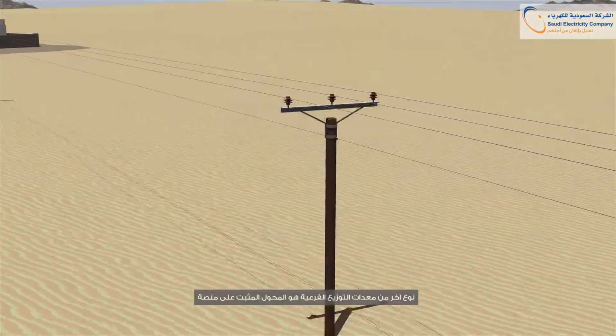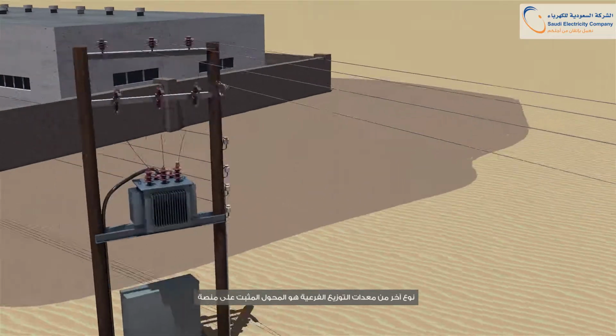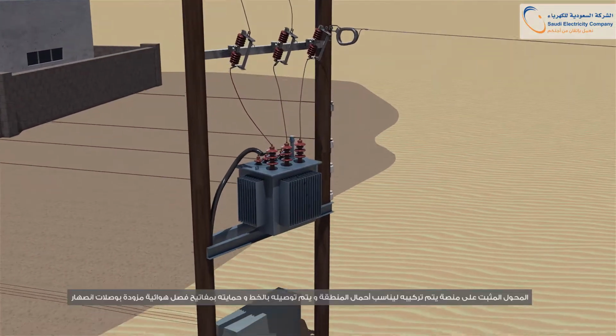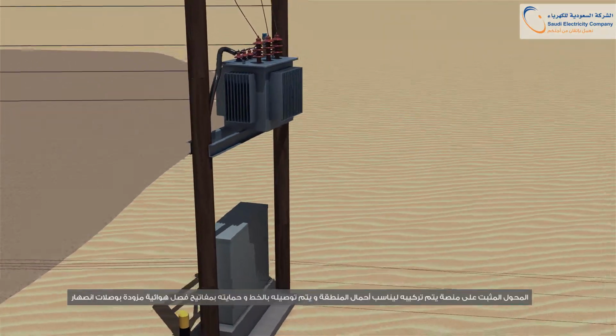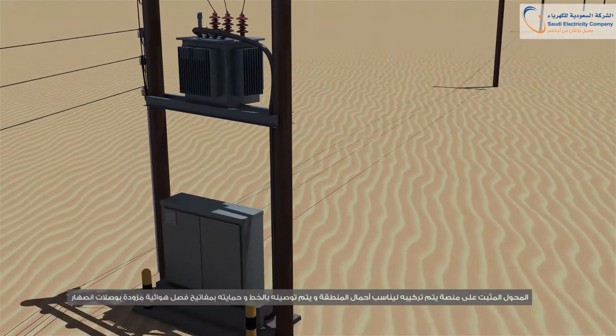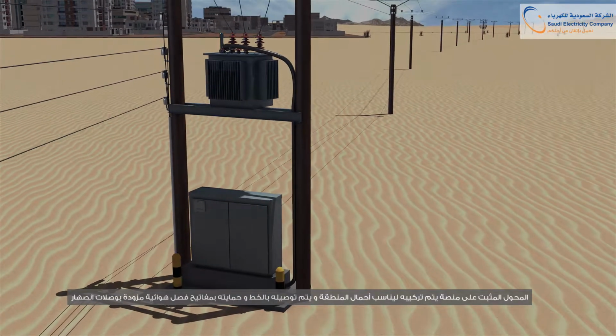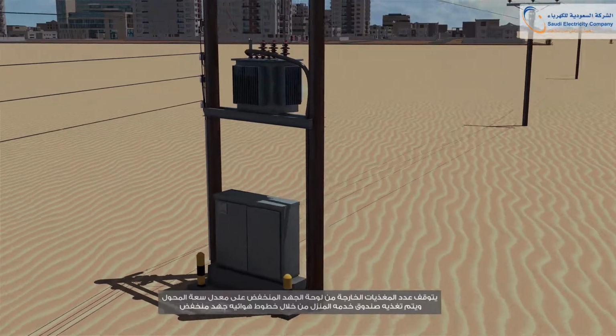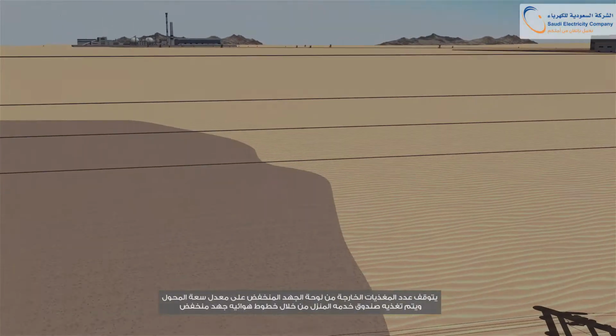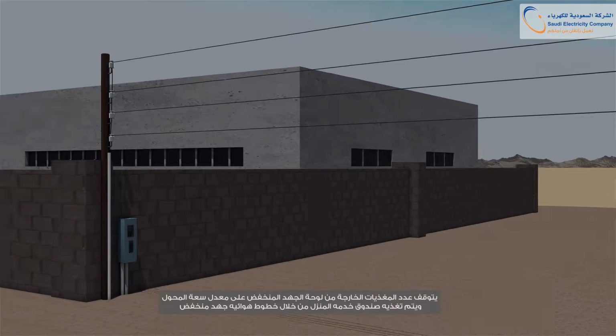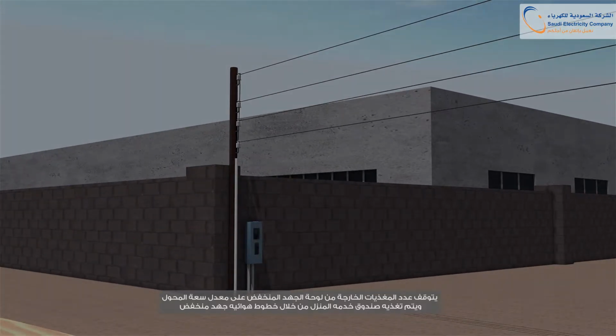Another type of distribution substation is a platform-mounted transformer. A platform-mounted transformer is fitted to suit the loads of this area and connected to the line and protected by disconnect switches fitted with fuse links. The number of LV panel outgoing feeders depends on the transformer rating and feeds the house service box through low voltage overhead lines.